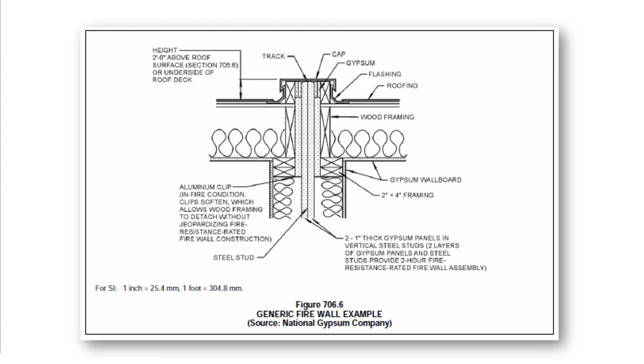So we've read the charging section for structural stability. The wall, again, has to be designed to remain standing, even if the buildings on the other side collapse. And then there's an exception for this in seismic design categories D through F, where double firewalls are used in accordance with NFPA 221. Floor and roof sheeting not exceeding 3/4 inch thickness shall be permitted to be continuous through the wall assemblies of light frame construction. So you heard me say that the roof cannot be supported by this wall and the floors cannot be supported by this wall, but there's a little bit of an allowance for this connection.